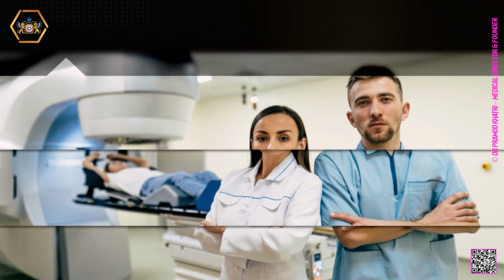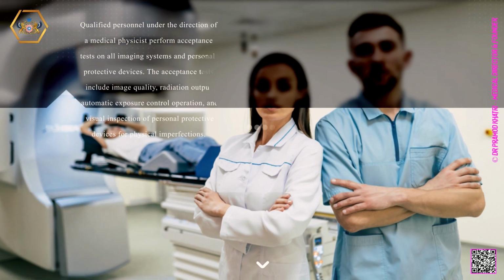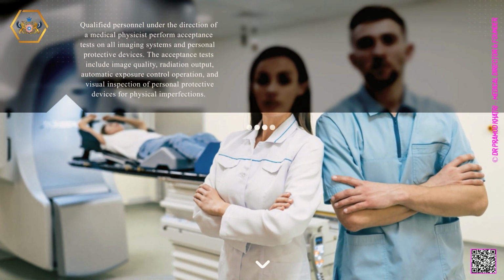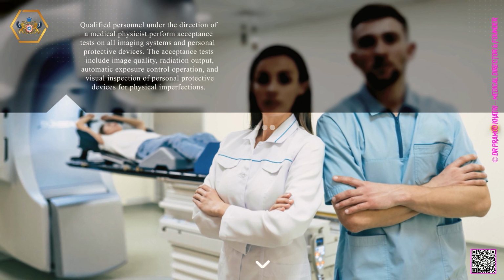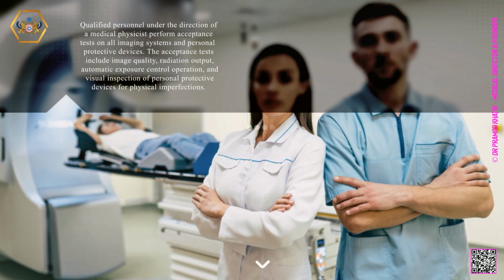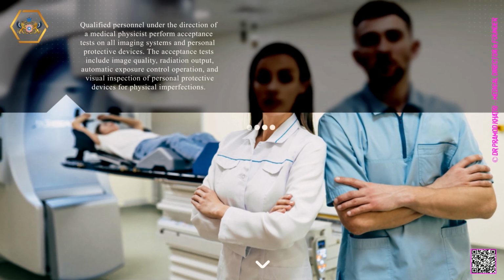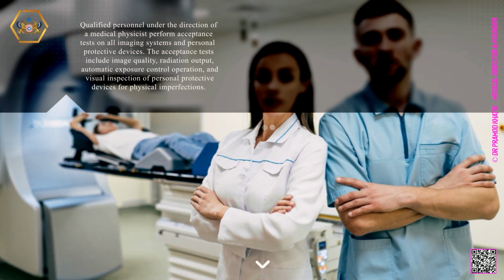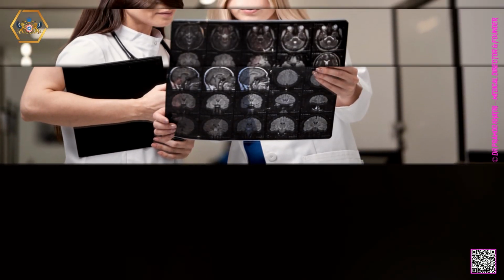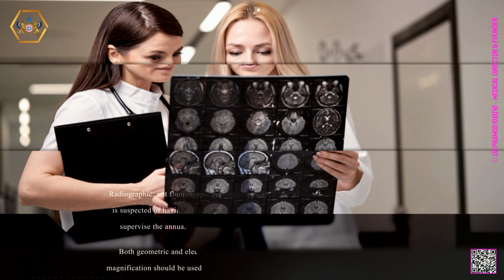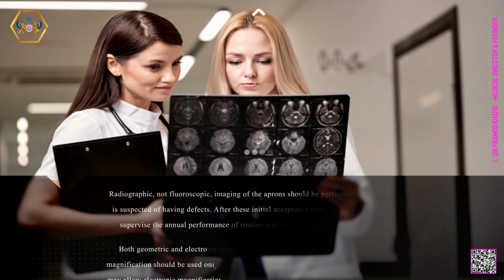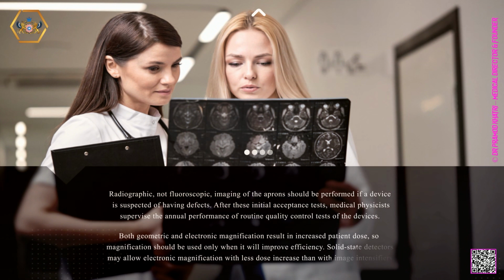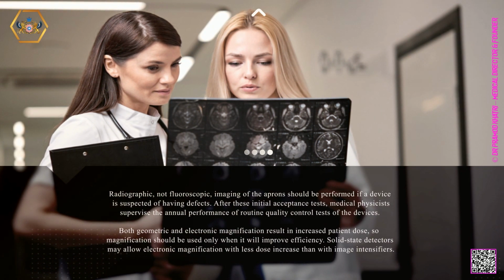Qualified personnel under the direction of a medical physicist perform acceptance tests on all imaging systems and personal protective devices. The acceptance tests include image quality, radiation output, automatic exposure control operation, and visual inspection of personal protective devices for physical imperfections. Radiographic, not fluoroscopic, imaging of the aprons should be performed if a device is suspected of having defects. After these initial acceptance tests, medical physicists supervise the annual performance of routine quality control tests of the devices.